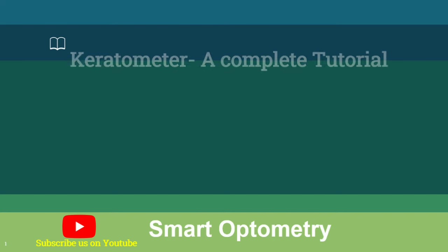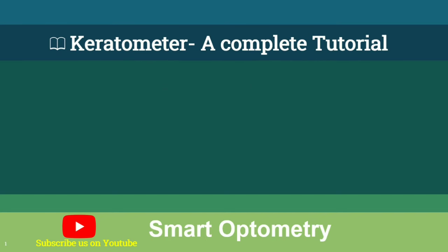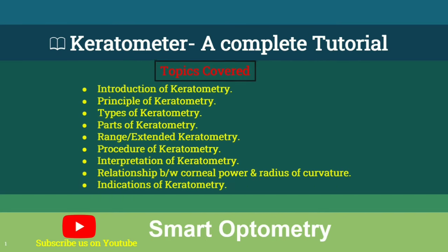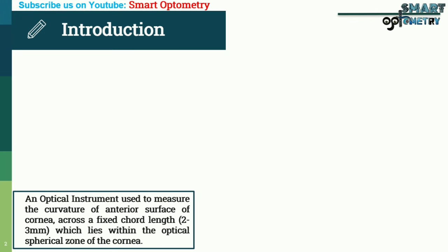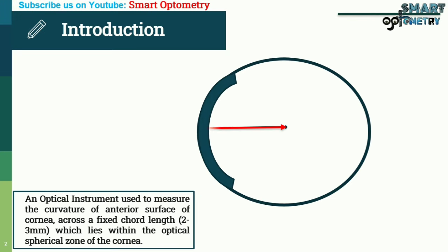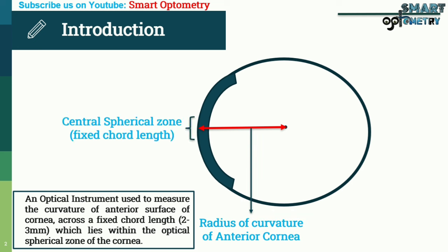Today I will discuss keratometry. A keratometer is an optical instrument used to measure the curvature of the anterior surface of the cornea across a fixed chord length of 2 to 3 mm, which lies within the optical spherical zone of the cornea.